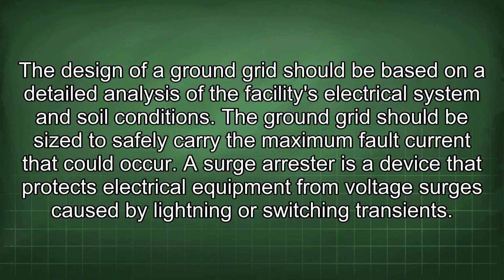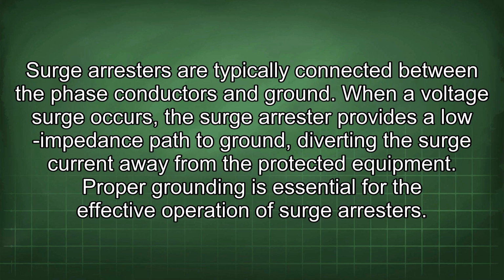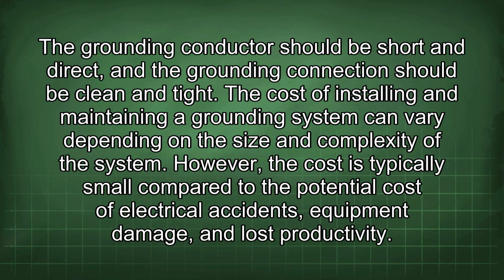A surge arrestor is a device that protects electrical equipment from voltage surges caused by lightning or switching transients. Surge arrestors are typically connected between the phase conductors and ground. When a voltage surge occurs, the surge arrestor provides a low impedance path to ground, diverting the surge current away from the protected equipment. Proper grounding is essential for the effective operation of surge arrestors. The grounding conductor should be short and direct, and the grounding connection should be clean and tight.